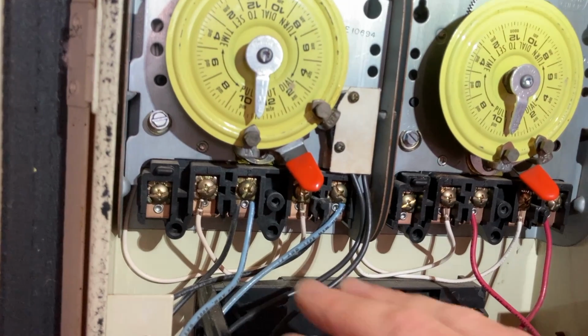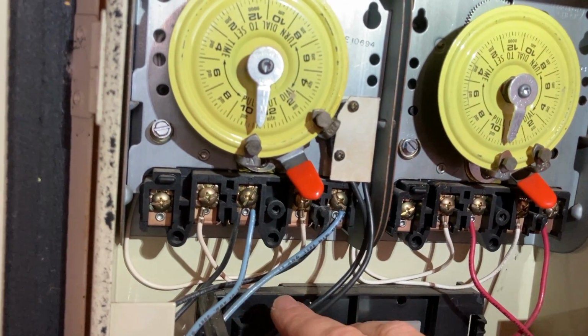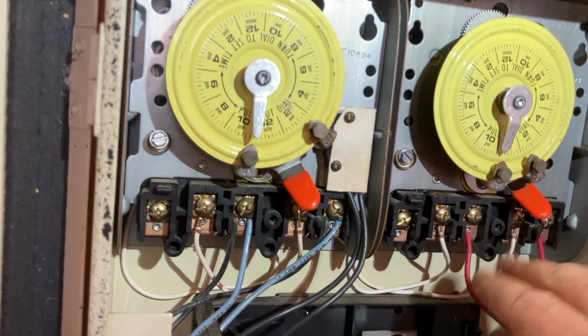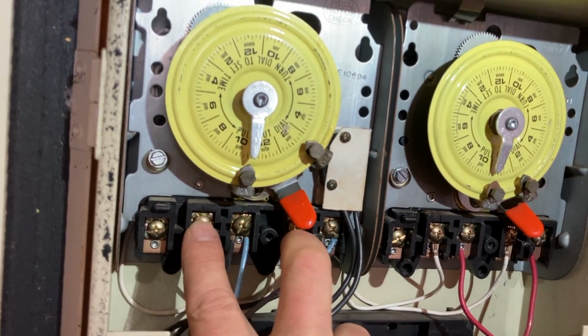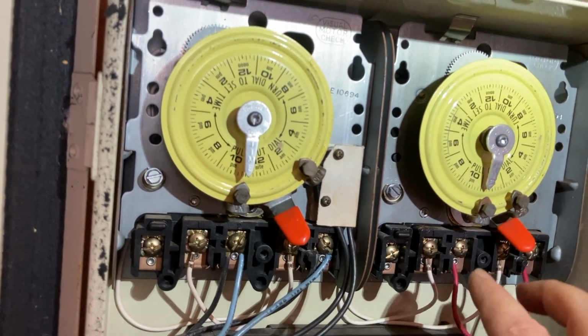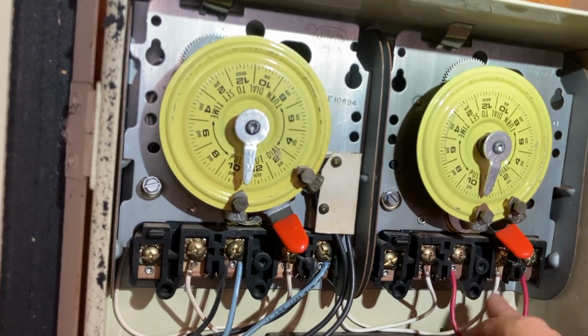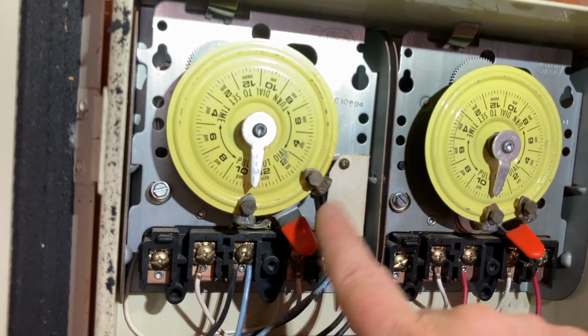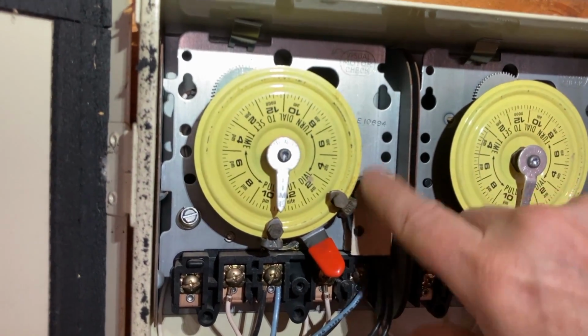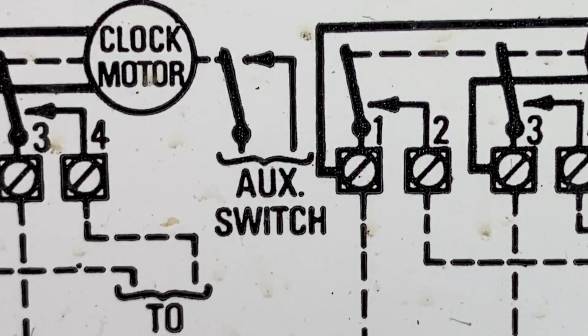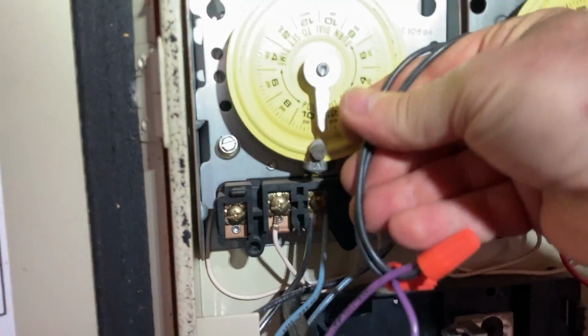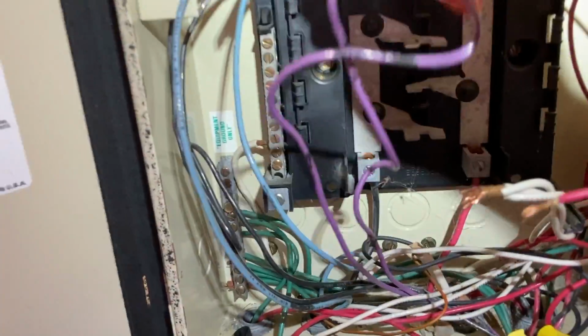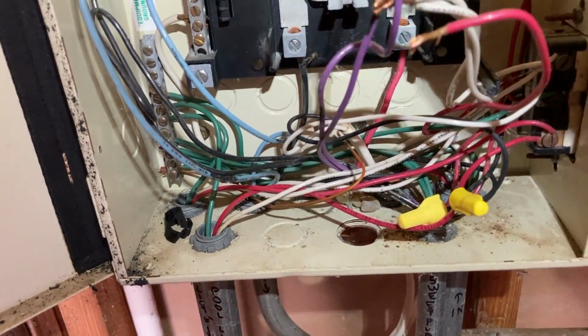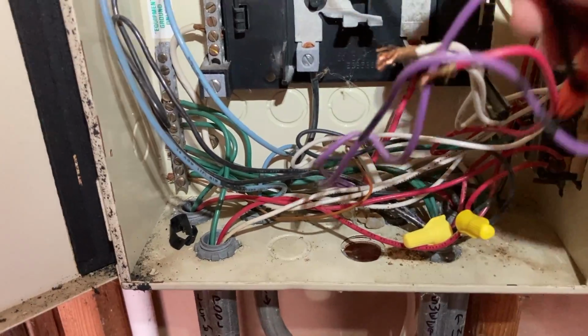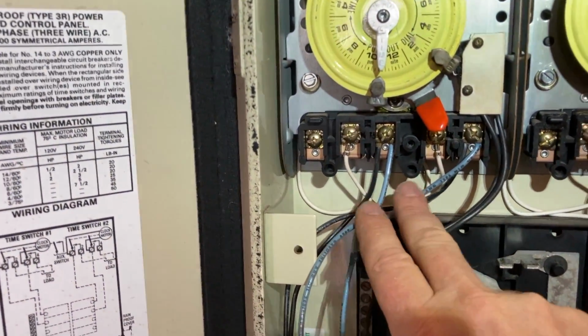So I came across something I wasn't expecting, although in retrospect it's probably pretty standard. These are the regular terminals for the timer—these two are in and these two are out, these two are in and these two are out—and the white wires are running the clock. But this timer has this extra switch, listed as the auxiliary switch on the list, and that's these black wires here that go to purple wires running down the conduit to the pool heater and the pool sweep motor. So not only do these blue wires turn on the pump...